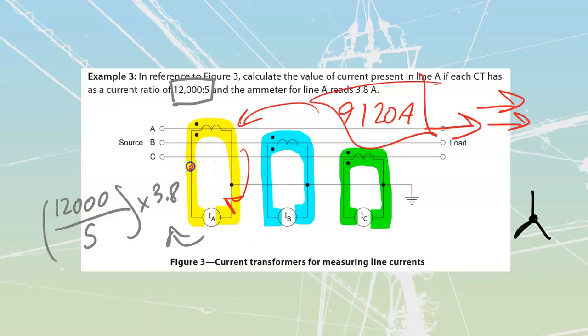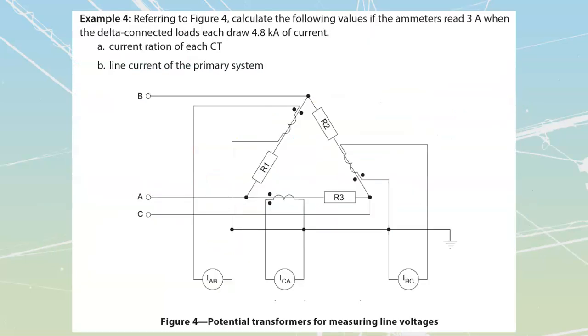That means that even if I were to short across here, we would never have more than, in this case, 3.8 amps flowing through that shorted bar and through these shorted out windings, because once again, it is the load over here that is pulling this 9,120 amps through here, which is then giving us this 3.8. This is why it's safe for us to short out a CT. And do we short out a CT? Absolutely. We always short out our CTs anytime we are going to pull the actual metering element out of here.